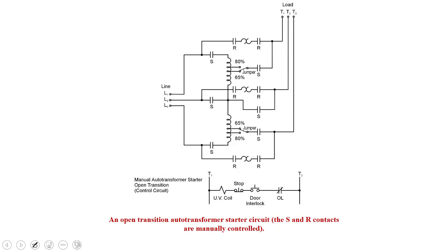Here's what an auto transformer would look like, and this one we are looking at is an open transition auto transformer. You see that there are 2 auto transformers in there, so it's basically an open delta made with 2 auto transformers. And so how does this work? Well, during the start period, the S contacts would close, energizing the auto transformer and allowing us to take the taps off, and we'd see 65% of the voltage. So this is a 3-phase auto transformer.